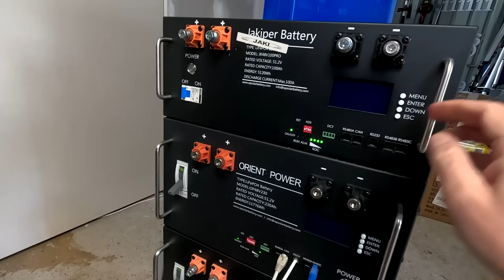So there is still a huge problem with the communication between master and slave batteries with the PACE BMS. Okay, I would say I'm refusing to test any further. So they need to do all the testing, and when they are confident everything works as it's supposed to, they can contact me again and give me a firmware which actually works. Until then, I would not recommend using this new PACE BMS with the Bluetooth and Wi-Fi functionality because it doesn't work. It has some serious issues with reporting the correct values to your inverter. And this could be potentially very, very dangerous.